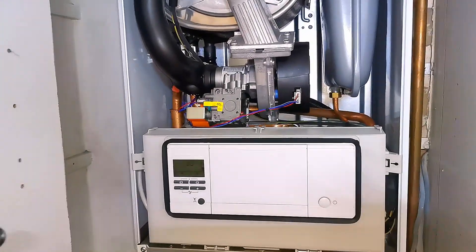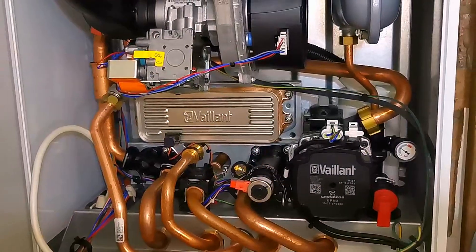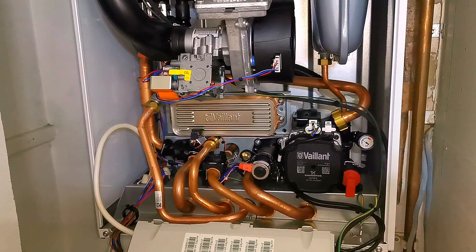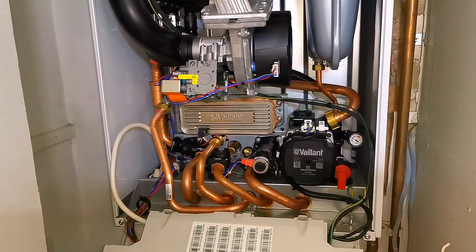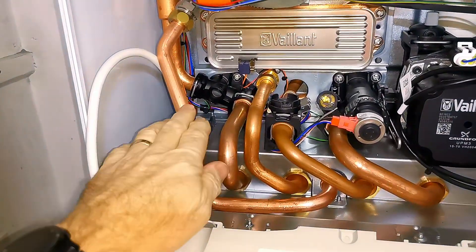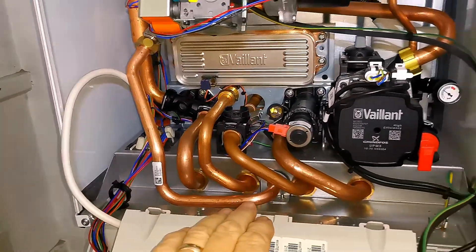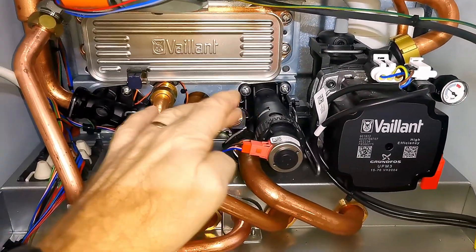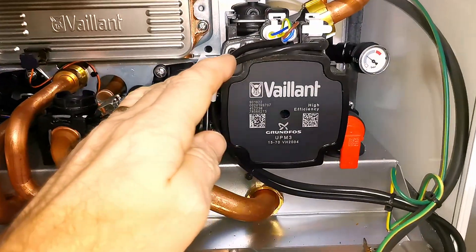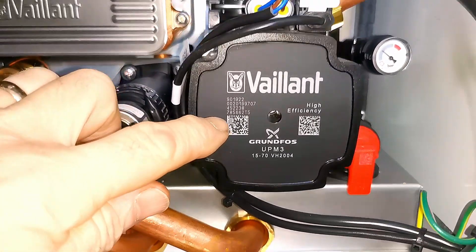Now let's take a look inside this boiler. I'll just fold down the front panel here, which holds the PCB. All these components are pretty much in every combination boiler these days — they may look slightly different and be made by different manufacturers. One of the things I like about Vaillant boilers is I can change most parts within the hour. They have a nice lot of copper pipes — so there's no plastic pipes in this boiler. We have our diverter valve here, which just switches between our hot water and central heating. We have our hot water flow sensor there. We've got a pump here, and this is a Grundfos pump — they're known as being one of the leading brands on the market.